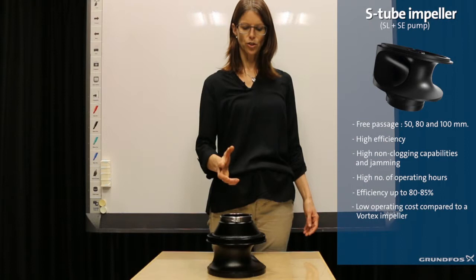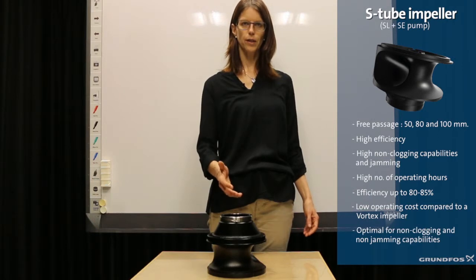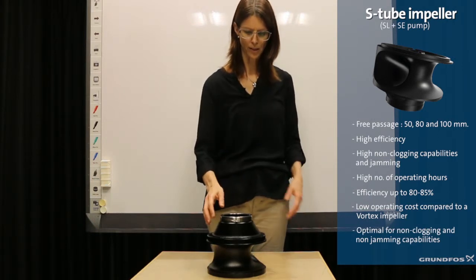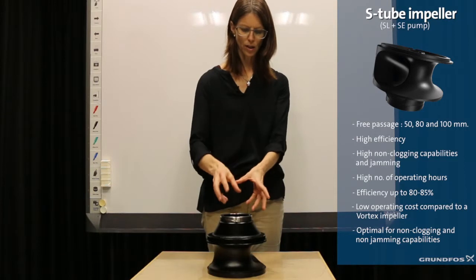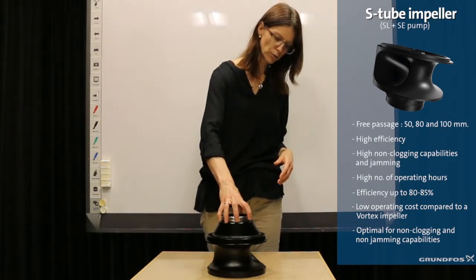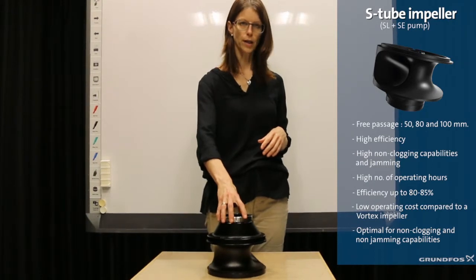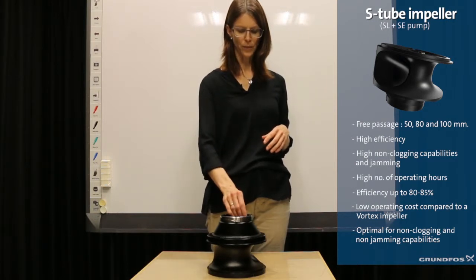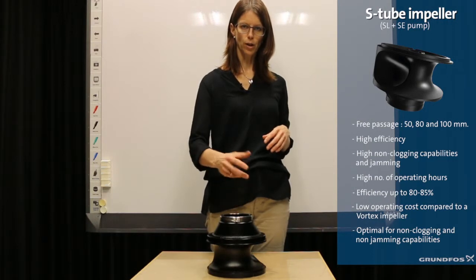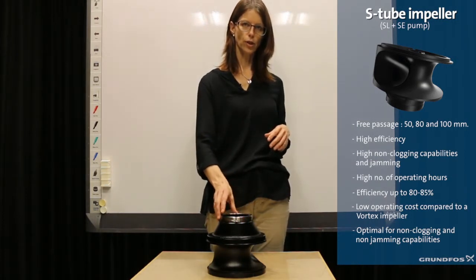The S-tube impeller cannot handle as much dry solids as the vortex impeller, though. This design is optimal for non-clogging and non-jamming capabilities. It not only has a very good free passage design, but also a spin-out groove between the pump housing and the impeller which reduces recirculation of the wastewater. Wastewater trying to run back is led into the inlet, and solids are cut into smaller pieces.